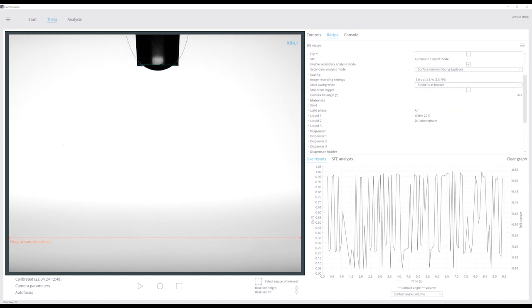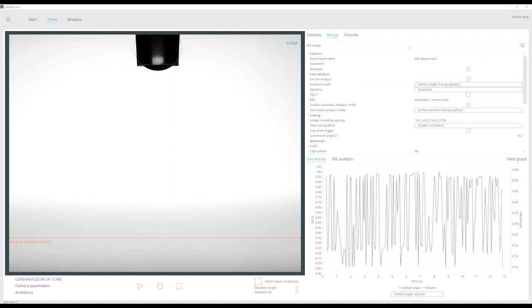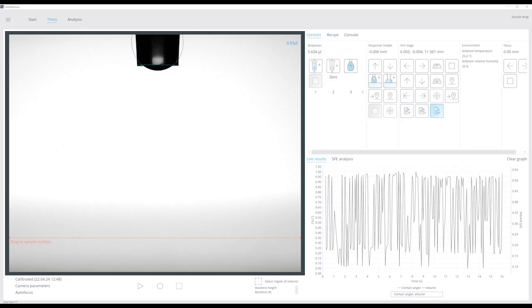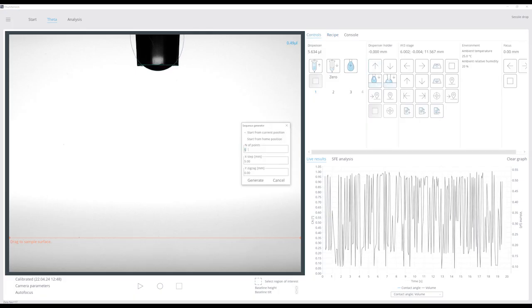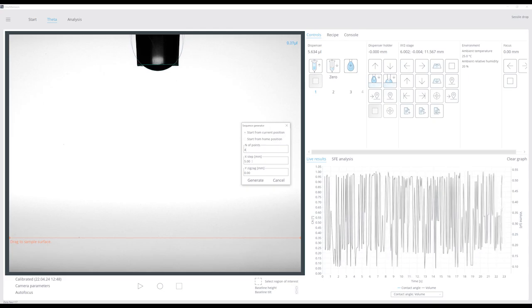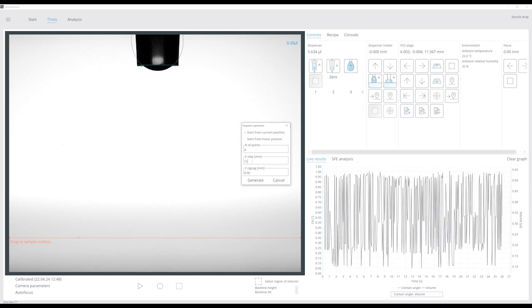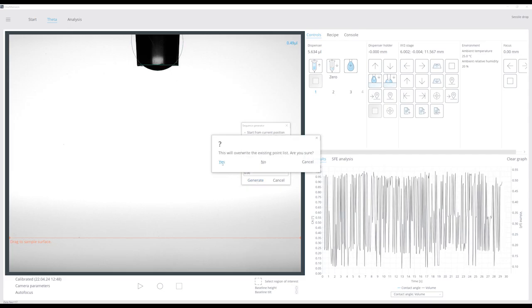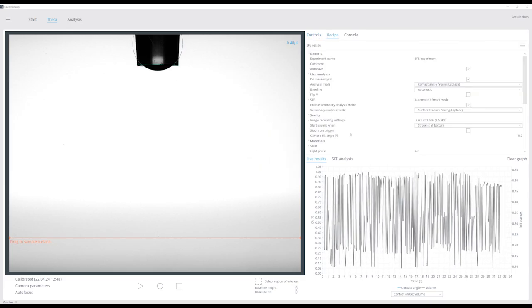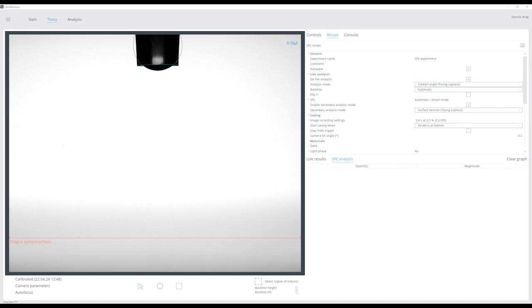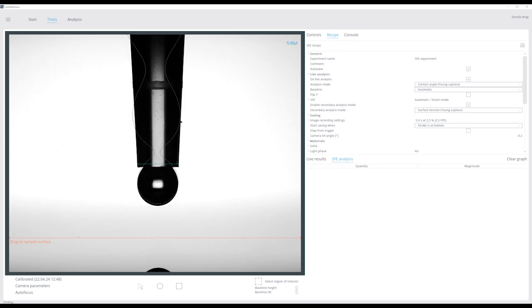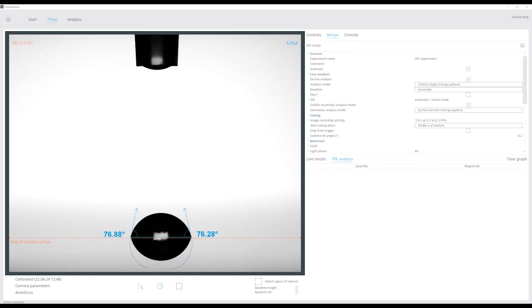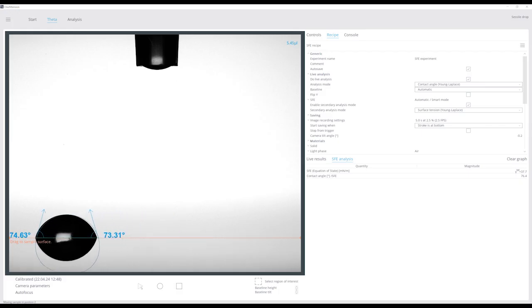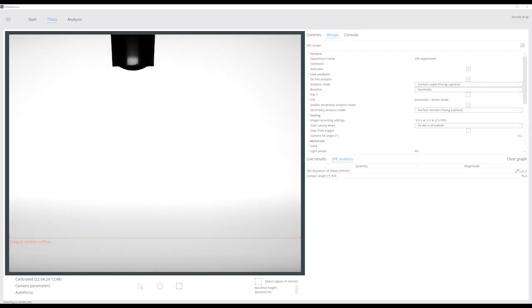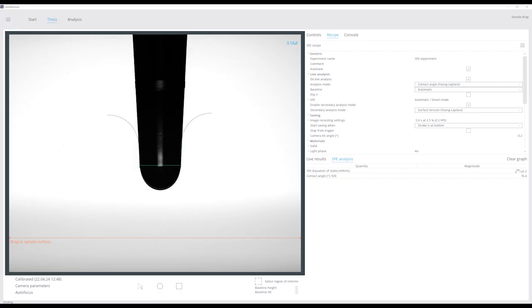As the instrument has an automated XYZ stage connected, it is possible to measure several contact angles in a row with both probe liquids. Here, 4 measurement points are defined. The measurement is started. The instrument will now measure 4 contact angles, 2 with water and 2 with diiodomethane. Both the sample stage and dispenser selector are automatically moved between measurements. The software will calculate the surface free energy automatically in real time.